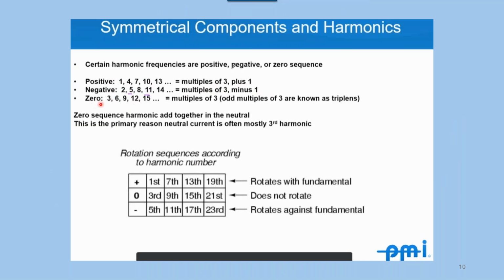And then we have zero sequence. Zero sequence is all the current that's going through the neutral or the ground. So we hear about people burning up neutrals because of harmonics. That's because we've got zero sequence current. There's also a subset of the zero sequence current called the triplens. The triplens are the odd multiples of 3, and I've got another slide on this, but that would be 3, 9, 15, 21.